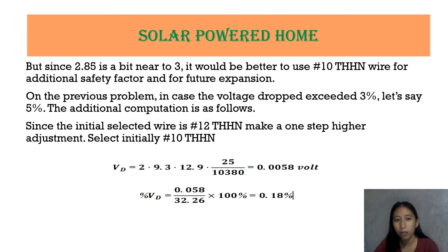So, sabi doon sa ating previous problem na in case the voltage drop exceeded 3%, sabihin natin na 5%, the additional computation is as follows. So, the initial selected wire is number 12 THHN. Make a one-step higher adjustment. So, mag-a-adjust tayo ng konti para magamit natin ng mas maayos yung wire natin. Select initially number 10 THHN.